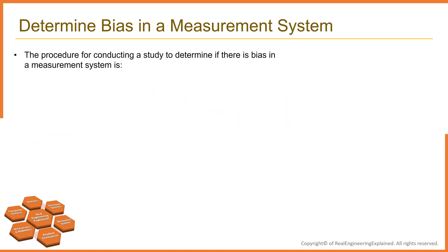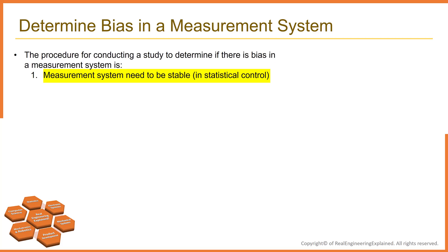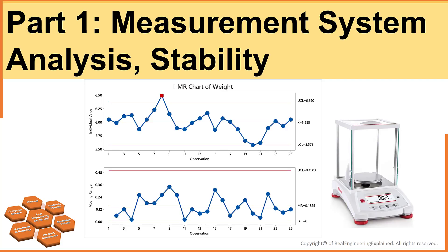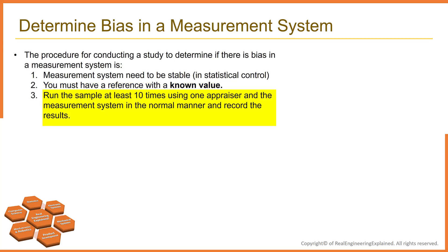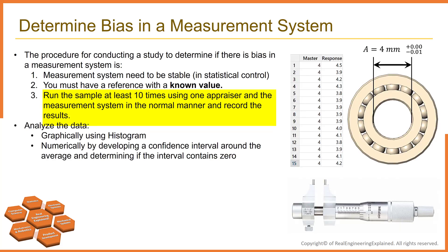The procedure for conducting a study to determine if there is bias in the measurement system is as follows. Step one: it is important that the measurement system be stable when the bias study is done. Step two: you must have a reference with a known value — a traceable standard; for example, scales often have weights that serve as standards. Step three: run the sample at least 10 times using one appraiser and the measurement system in the normal manner and record the results. The more times you run the sample, the greater the accuracy of the bias study.